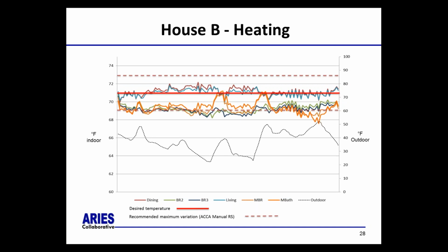House B, we dropped a little bit in some rooms because of the variability in distribution systems. Probably the design of the distribution systems was not completely balanced with the heat loss in the rooms. So as a result, we have a little bit of underheating in the bedrooms, but not too bad.